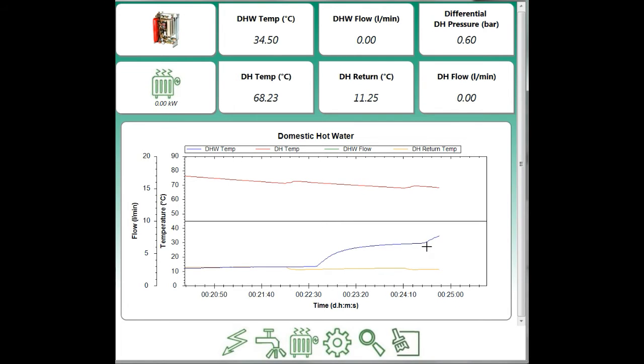You'll notice that the district heating flow temperatures are dropping. That's because of the heat losses from the branch pipe work connecting up to the HIU. They're losing heat quicker than the water in the HIU. Now we can see the second pulse is rising and it's starting to level off.